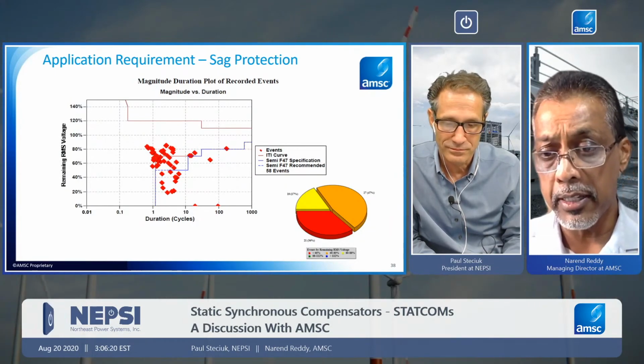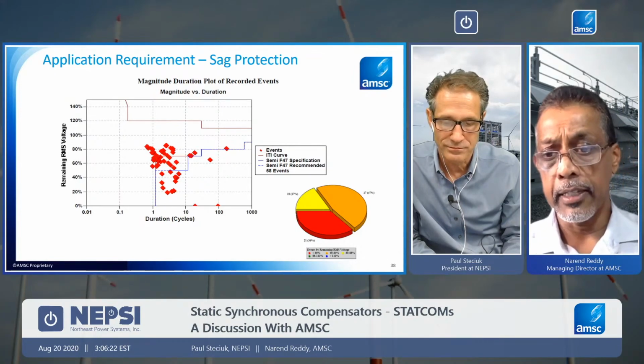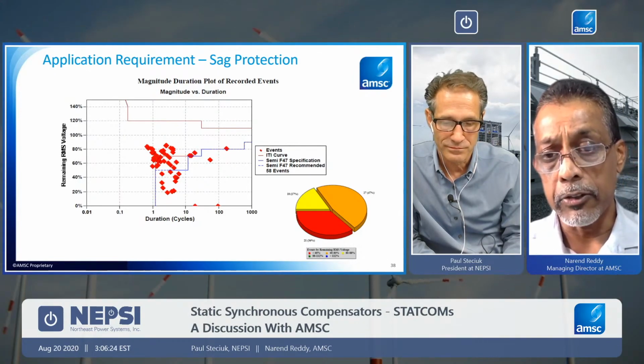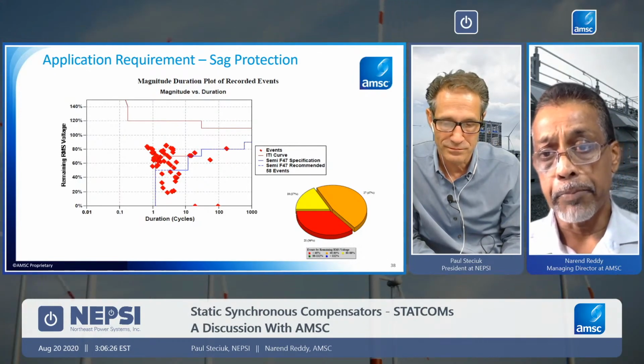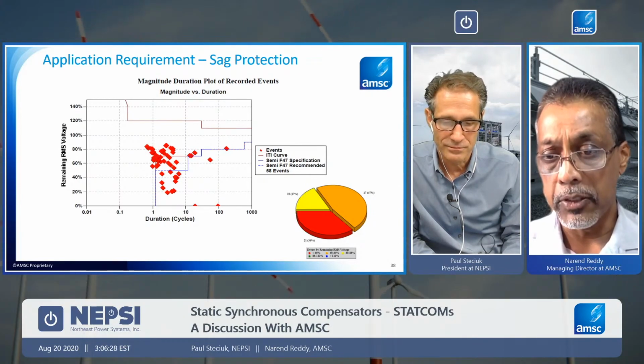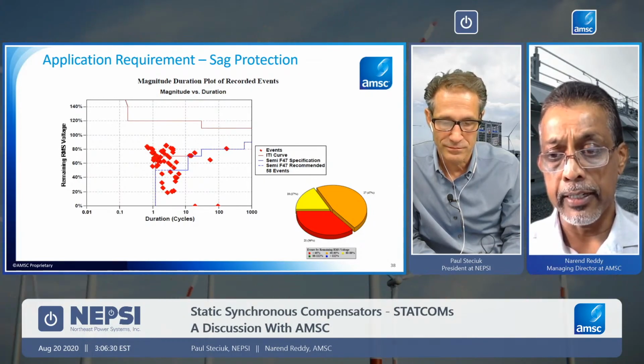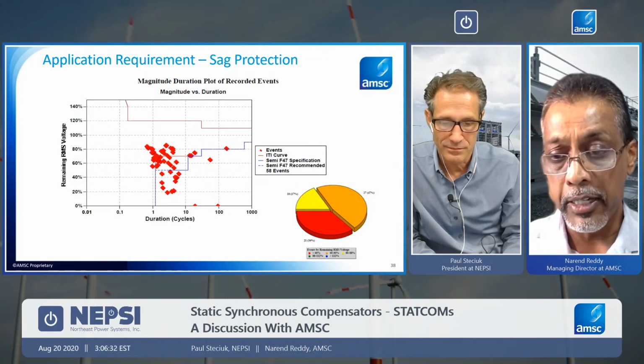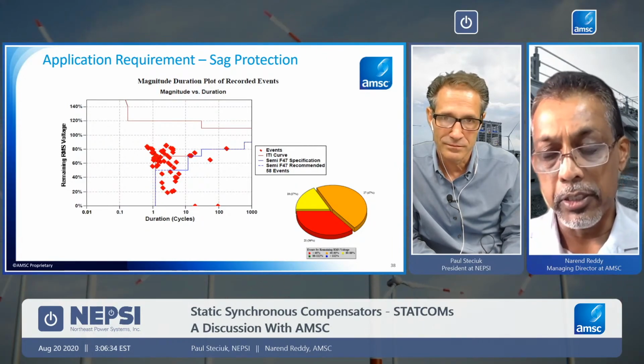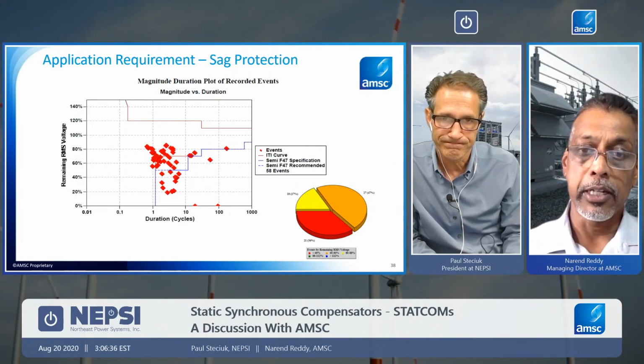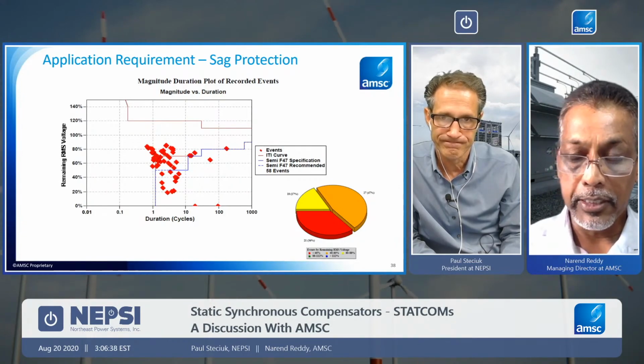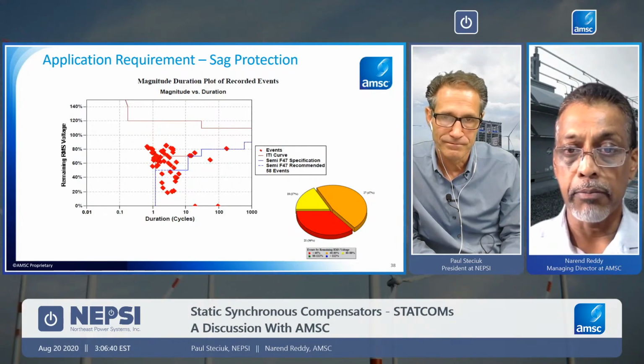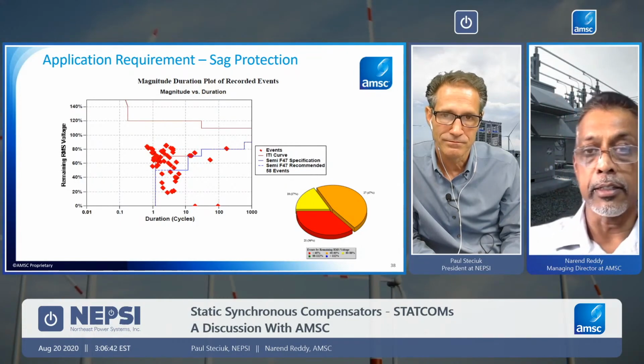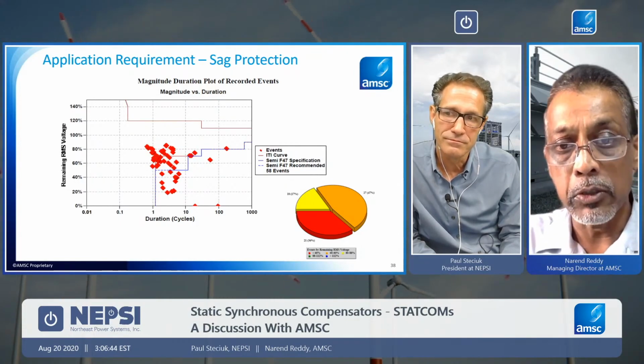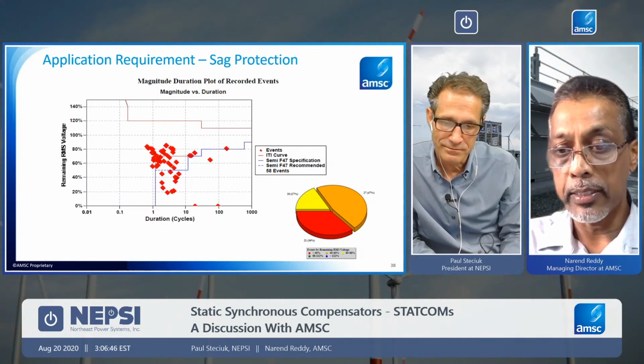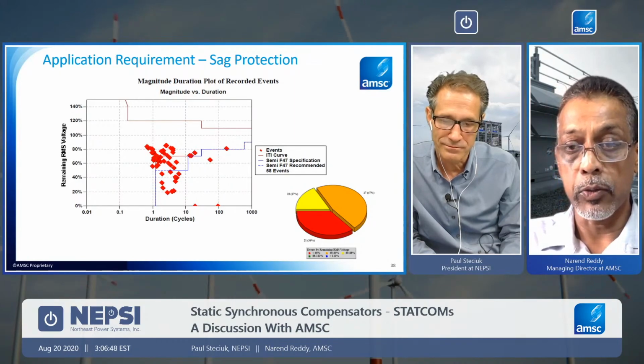There are certain instances that may be unavoidable. For example, you do have two of those events that are sitting at 0% voltage, which are basically reflecting either a very close-in fault or an outage of the system for a momentary outage. It's difficult to raise a voltage that's zero. So barring those ones, I guess the objective of the system would be to improve on the ones that are outside of the required band.